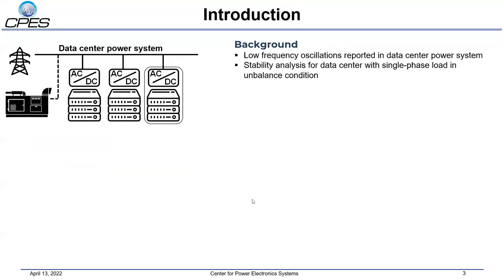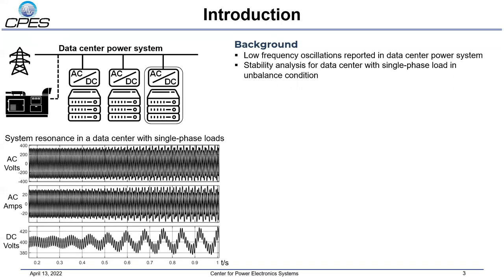A data center power system is a typical power electronics-based power system, where the grid or backup generator supplies power through a three-phase power distribution network for numerous power supply units (PSUs), which contain a single-phase power factor correction (PFC) and an isolated DC-DC converter. The dynamic interaction among non-ideal sources and a great many converters may bring instability to the system, including low-frequency oscillations. Several Facebook data centers have been reported to suffer from low-frequency resonance instability under a certain configuration of the distribution system. To better understand and avoid similar unstable phenomena, it is important to model and perform stability analysis of such systems.